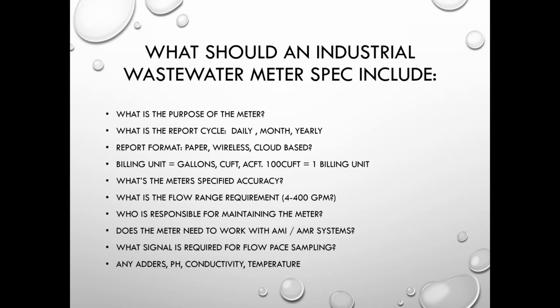We also need to identify who is responsible for maintaining the flow meter. Many times they'll install the meter and the response is, I don't have the confined space entry equipment at the facility because I'm just the maintenance manager. I don't know if I'm supposed to be responsible or if I have to hire a contractor to do that. So that needs to be identified as well. Does the meter need to work with an automatic meter reading system or AMI system?